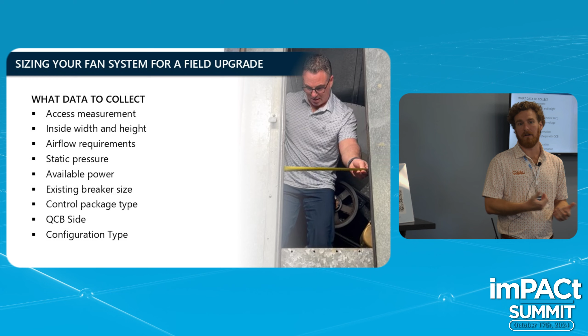Let's say you start at 2 inches of static and 35,000 CFM, and the total horsepower of the system is some value. If you just increase the static pressure, you'll see that horsepower increase as well. And if you get to a point where it matches what's existing, that's usually a pretty safe bet for a budget. But budgets are one thing; when you really want to order the system, you need to do more digging and research into what's existing. As far as the scope, the engineering of the project does fall on the rep or on the person purchasing the product. So that's something to be aware of.